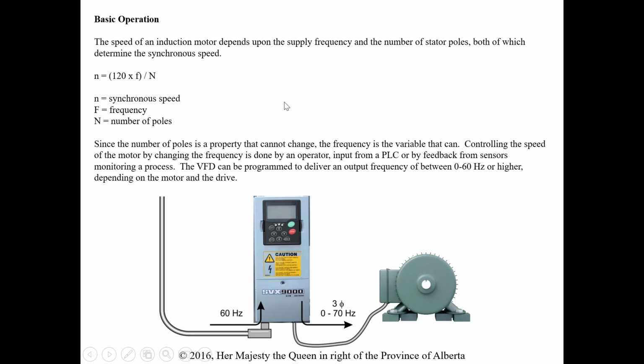So if we control the motor by changing the frequency, we can do that by an operator, input from a PLC, or feedback from sensors on a monitoring process, just like we talked about previously. And it can be programmed to deliver a frequency between 0 and 60 hertz or higher. Okay, so again, we can sit right at this nameplate, this display here, and change the speed manually, or it could be done remotely. Or it could be done from feedback from the motor. Okay, so we'll talk about open and closed loop control coming up later too.